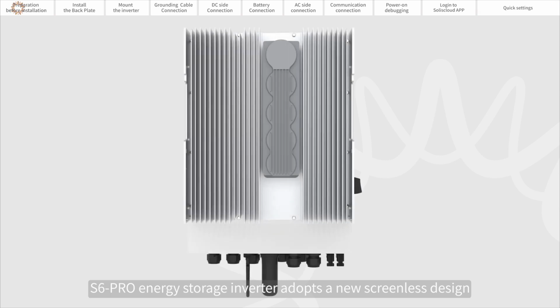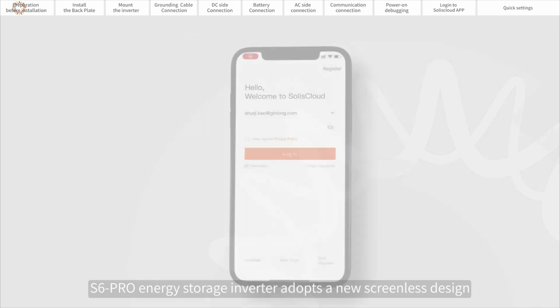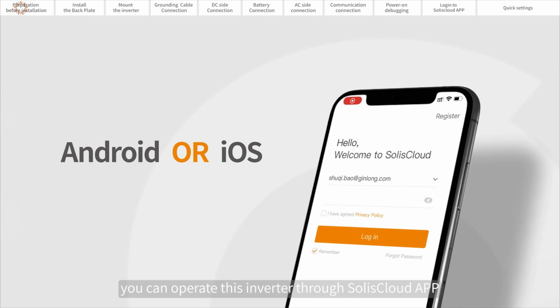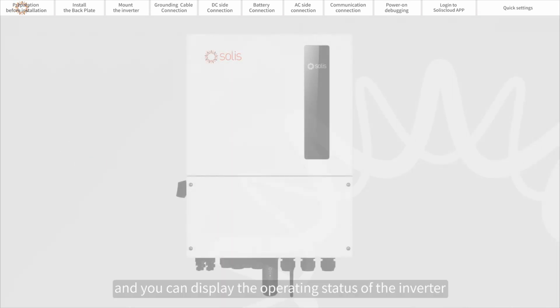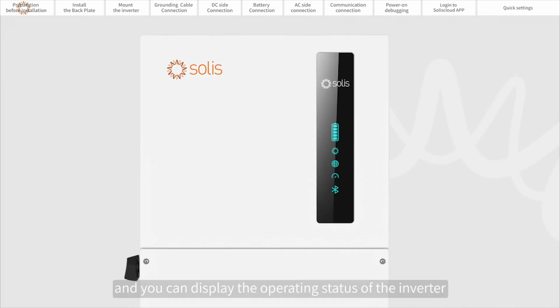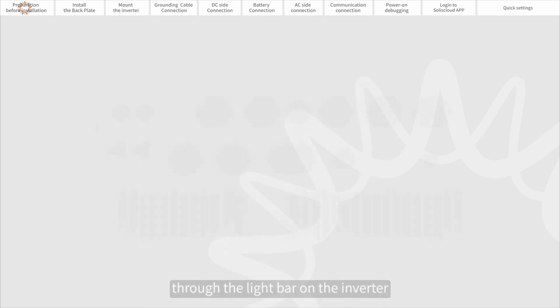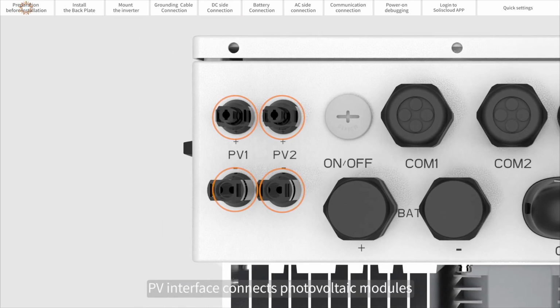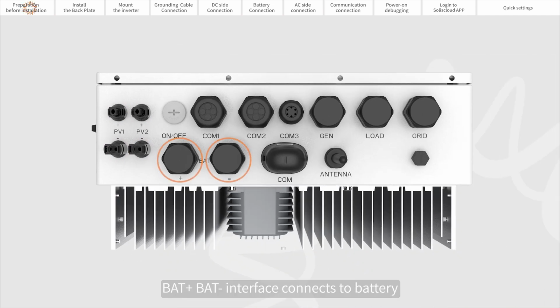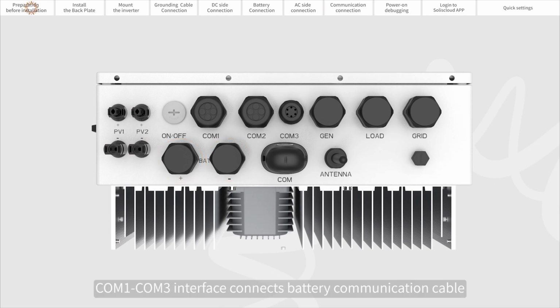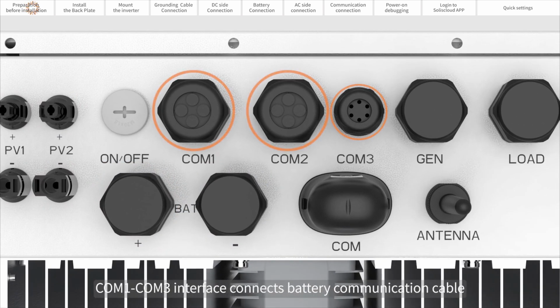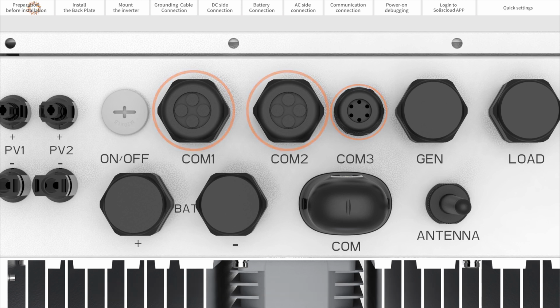The S6 Pro Energy Storage Inverter adopts a new screenless design, and you can operate the inverter through the Solis Cloud app. And you can display the operating status of the inverter through the light bar on the inverter. The PV interface connects photovoltaic modules. Input photovoltaic energy into the system. BAT plus and BAT minus interface the battery. COM1 through COM3 interface connects the battery communication cable, the CT wire, the parallel cable, and the generator communication cable.